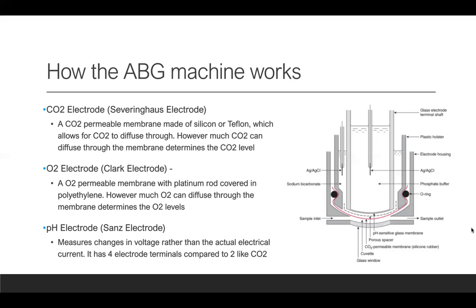So the O2, like I said, is the same thing, but it's a membrane with a platinum rod covered in polyethylene. And then the pH electrode, which is called the Sanz electrode, measures changes in voltage rather than the actual electrical current. It has four electrode terminals compared to two, like the CO2. There's a glass membrane that separates two solutions differing in pH. It measures the change in hydrogen concentration across the pH sensitive glass membrane. So those are the three electrodes that are in an ABG machine.